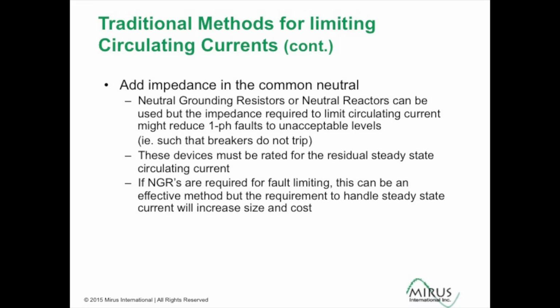But they do affect the fault level. You can also use neutral reactors as well. If they're inserted directly in the neutral, then they will affect the fault level. Sometimes we want to limit the fault level, but we need to understand that that's exactly what we're doing. If we're putting devices into the system that restrict the fault level, and we're not aware of that, then we could possibly limit the faults to levels that won't allow the protection to trip. The other point is these need to be rated for the residual steady-state circulating currents. So NGRs typically are rated for instantaneous currents, fault currents, not often rated for the continuous circulating currents. So you need to put in much larger, much more expensive devices when you need to address the circulating currents.